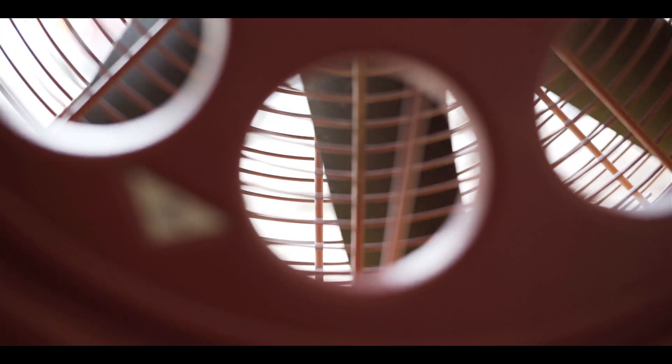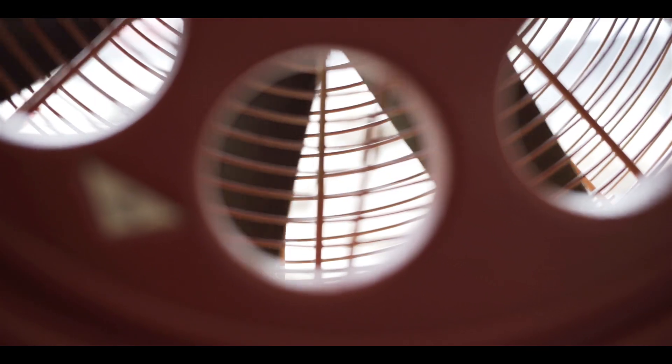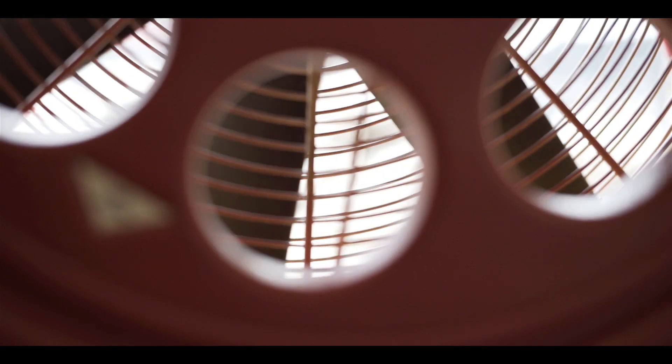This house that we just did today is coming in at about 1.5 to 1.6 air changes per hour, so that's a very good score.